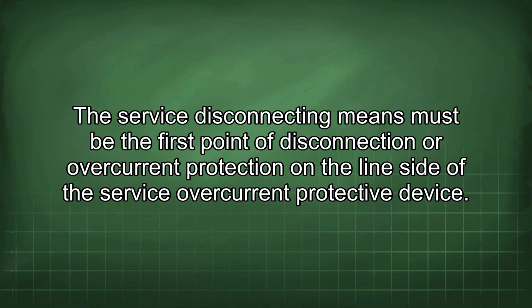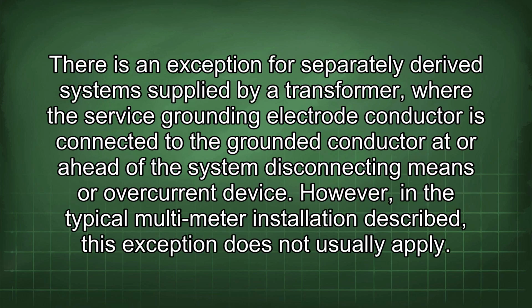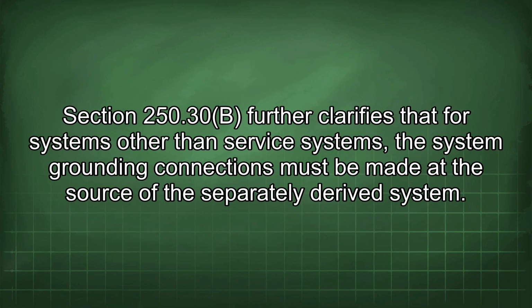Service disconnecting means must be the first point of disconnection or overcurrent protection on the line side of the service overcurrent protective device. There is an exception for separately derived systems supplied by a transformer, where the service grounding electrode conductor is connected to the grounded conductor at or ahead of the system disconnecting means or overcurrent device. However, in the typical multimeter installation described, this exception does not usually apply. Section 250.30(b) further clarifies that for systems other than service systems, the system grounding connections must be made at the source of the separately derived system.